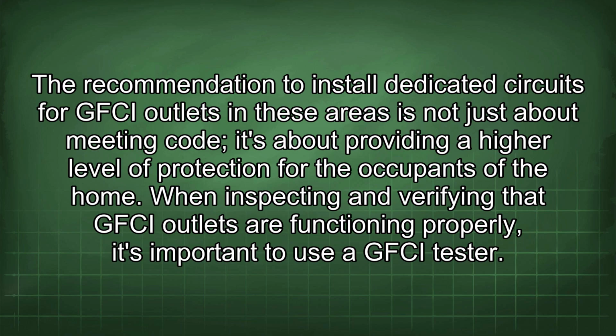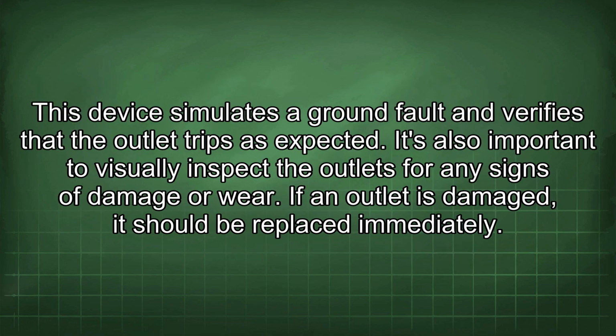When inspecting and verifying that GFCI outlets are functioning properly, it's important to use a GFCI tester. This device simulates a ground fault and verifies that the outlet trips as expected. It's also important to visually inspect the outlets for any signs of damage or wear. If an outlet is damaged, it should be replaced immediately.